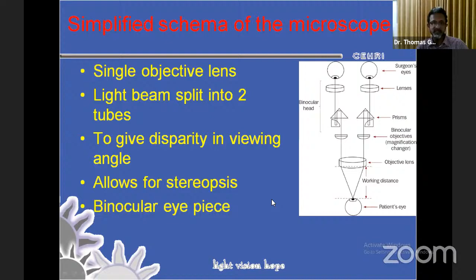Then it goes through a set of prisms to eyepieces, which are adjustable in terms of IPD and things like that. This disparity between the two ends of the lens is what gives you the stereopsis, and it allows for good stereoscopic visualization so that we can operate with depth perception. The working distance is decided by the objective lens, and for ophthalmology, in general, we have a long working distance of around 15 to 20 centimeters. That's why all the instrument handles are around this length. If it's any more than that, it will hit the microscope itself, which is not sterile.